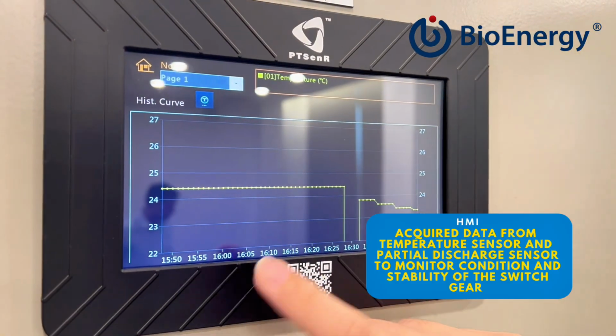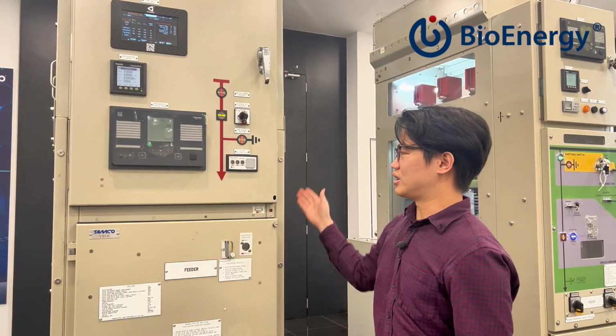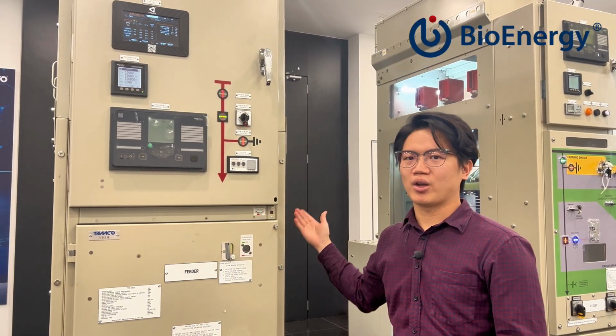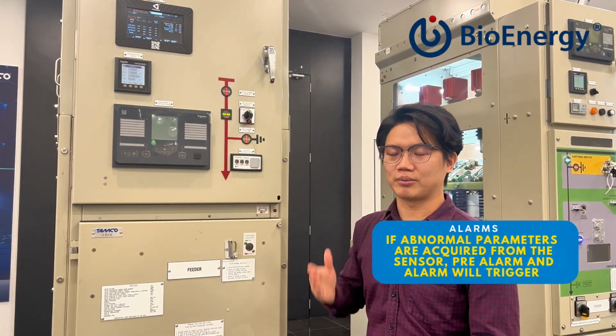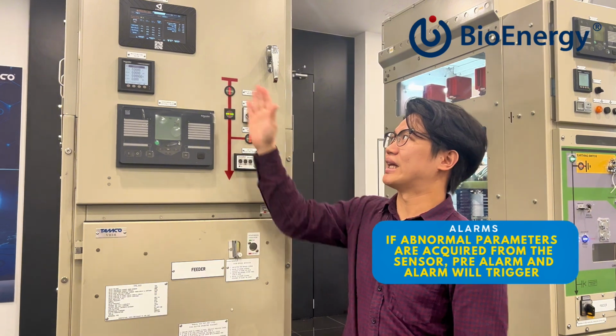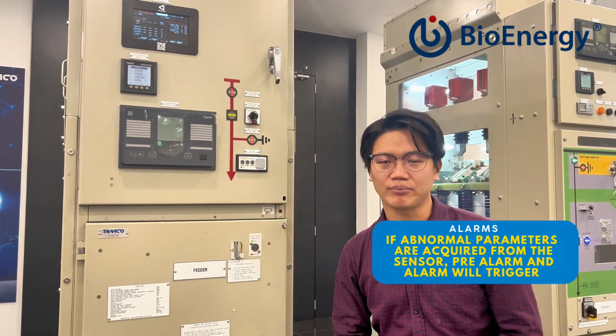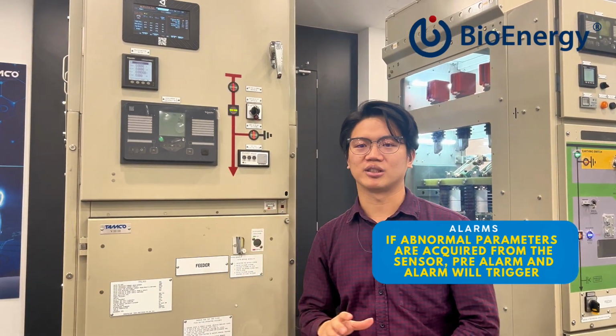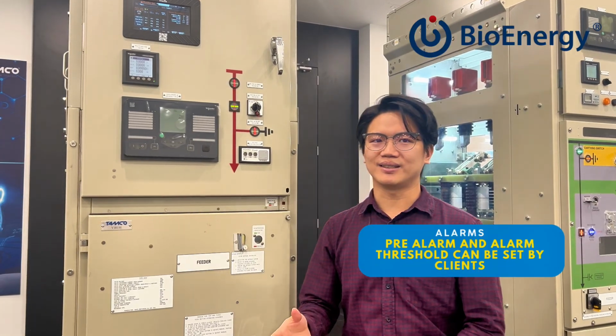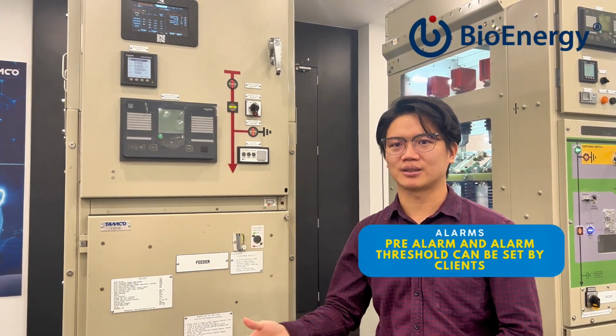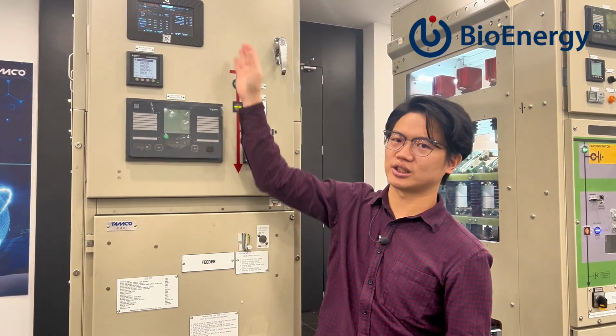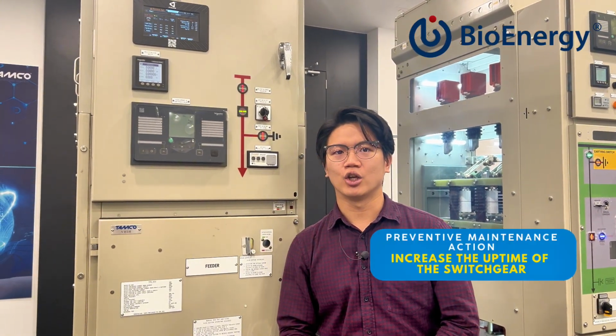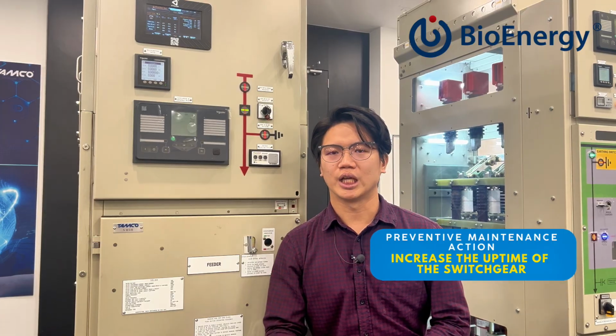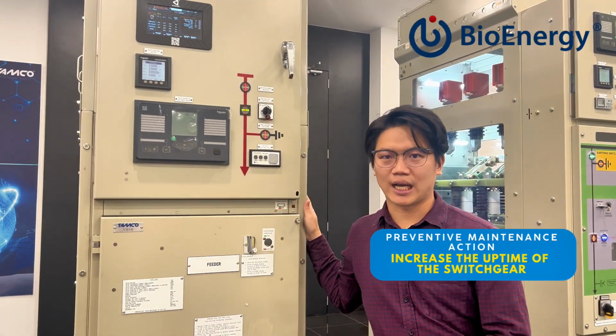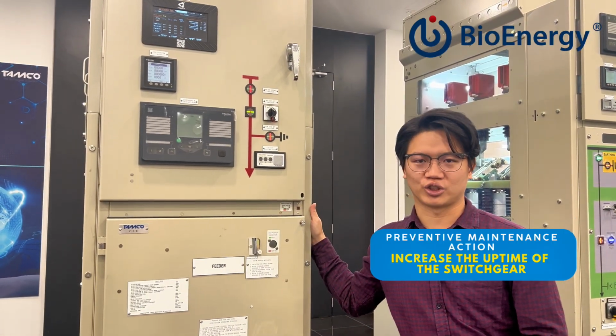So in case the HMI receives abnormal parameters, be it partial discharge or abnormal temperatures, then it will actually trigger a pre-alarm and an alarm. This threshold can be set by the clients. When these abnormal parameters are collected, it will actually trigger a preventive maintenance action for the client. So what should the client do in order to have a higher uptime for all their switchgears?